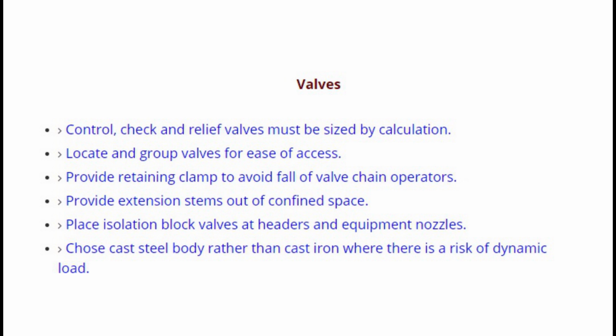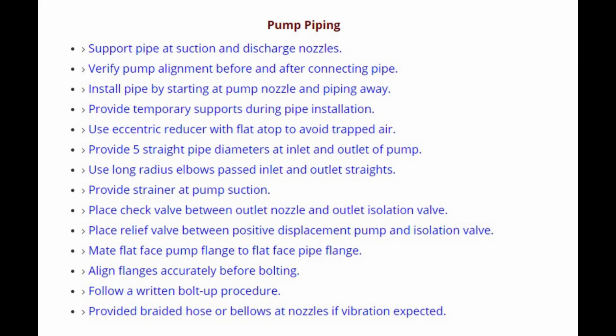Number 5. Place isolation block valves at headers and equipment nozzles. Number 6. Choose cast steel body rather than cast iron where there is a risk of dynamic load. Good practice for pump piping.